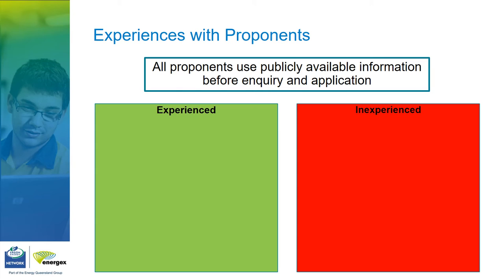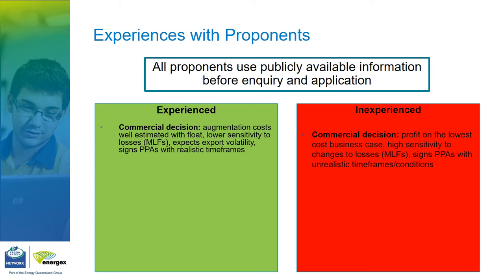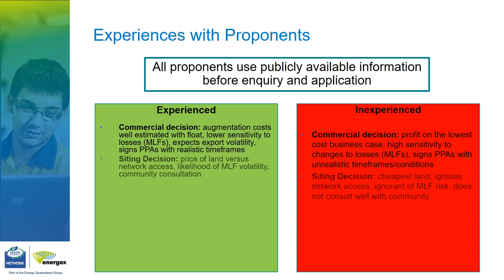So in the previous slide, I mentioned that TNSP connection experience does not automatically translate to DNSP connection experience, just due to the inherent differences in our networks. So this slide compares our EQL experiences with a multitude of proponents of varying skill sets and experiences. So basically what's good or bad, so that future proponents can avoid some of the common pitfalls that we see. So an experienced proponent would consider the commercial risk. They now have lower sensitivity to marginal loss factors, export volatility, and look at realistic timeframes for connection. Things like siting decisions will take into account possible system strength issues and ease of connection access, as well as having effective community consultation.